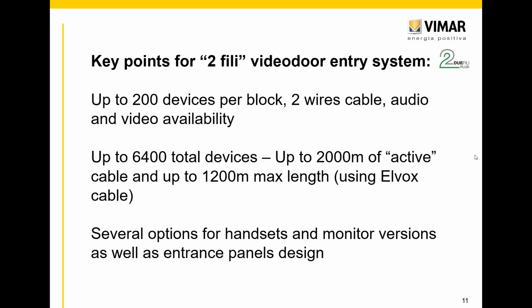Then we have also the Due Fili video door entry system, because it can also be integrated. The digital two-wire Due Fili system is capable of managing up to 200 devices per block, with a total limit of 6,400 devices, with up to 2,000 meters of cable active in the call.